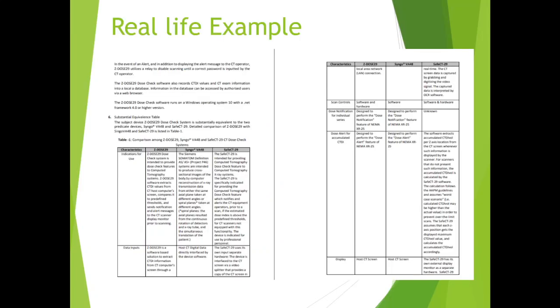Now, let me use a real-life example to show you how to craft an effective substantial equivalence table. Shown here is in section 6. This is part of the summary. And this section 6 is the detailed table for the comparison of our device to the predicate device.